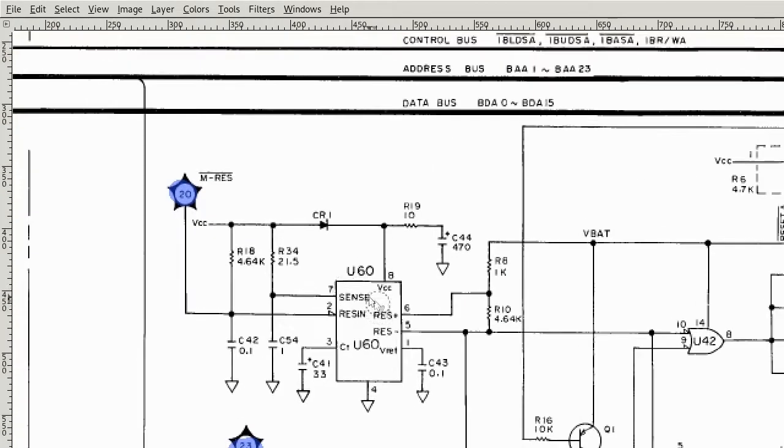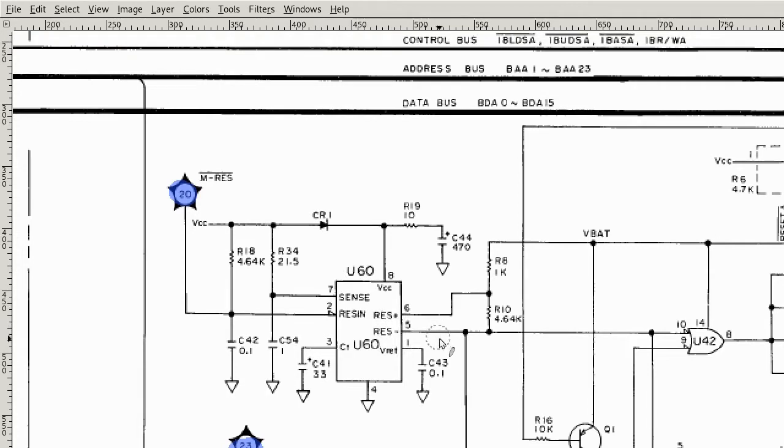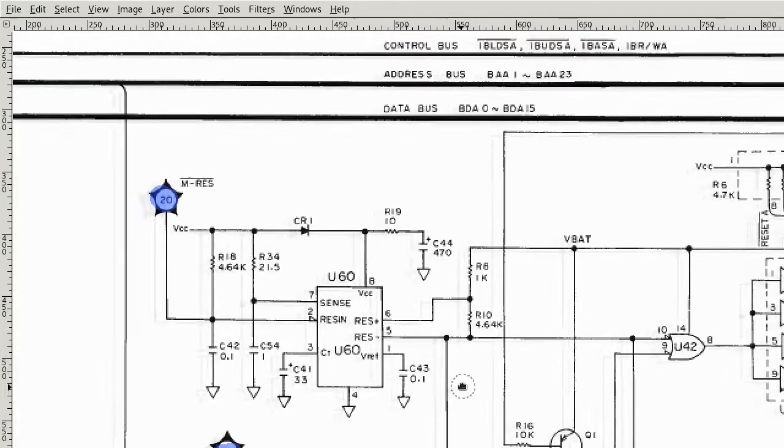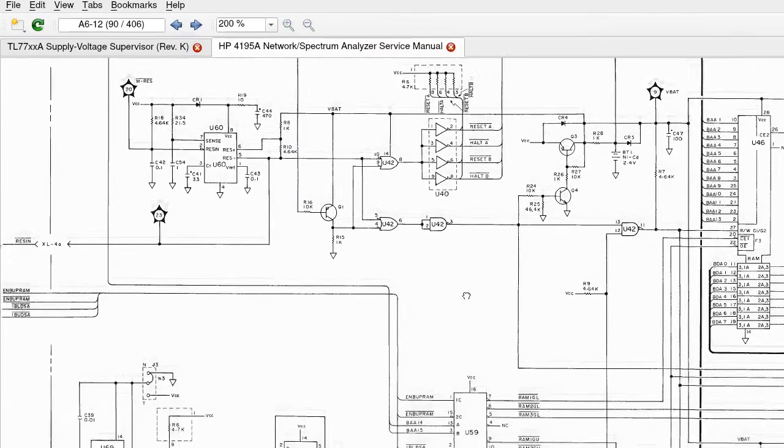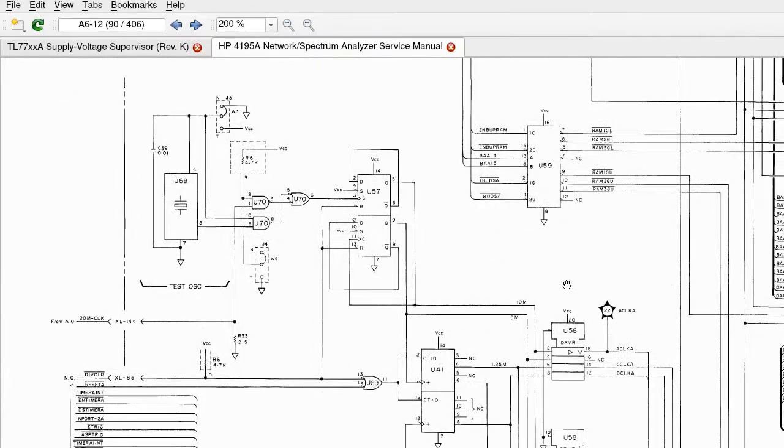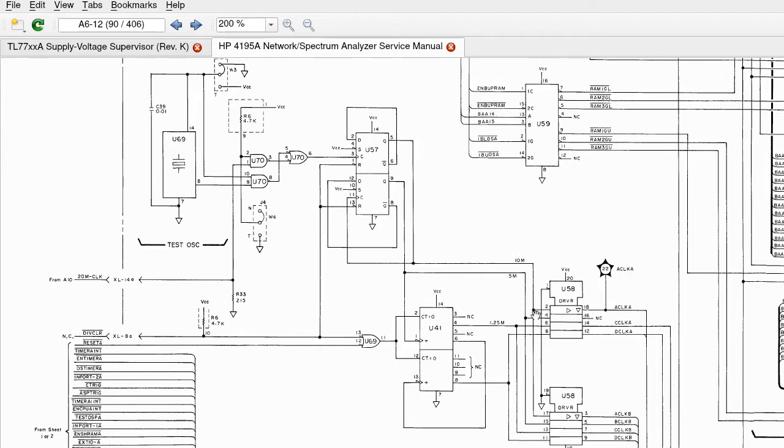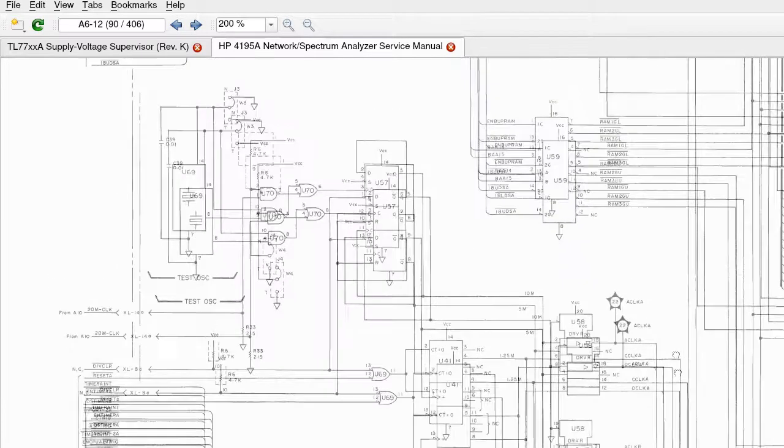The other place this goes to is the U60 output. So I'll just zoom in here. So U60 is a voltage supervisor with two reset outputs. One of them is active low, the other one active high. So on the active low output, I was reading plus 5. I'm sorry, I was reading plus 4.8. And also in the same area, I'll take a look at test point 22 here, which is clock A, which goes to the CPU on this same board. And I would expect to see 10 MHz here from a clock divider.